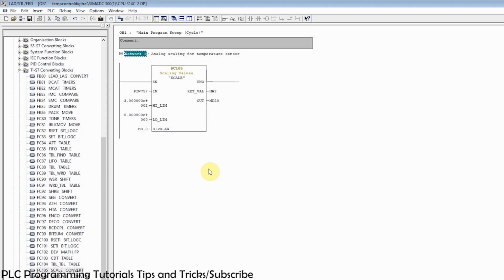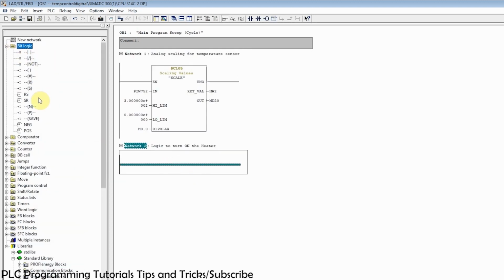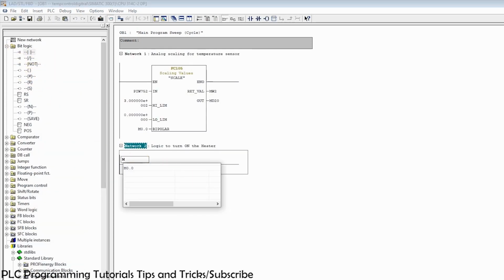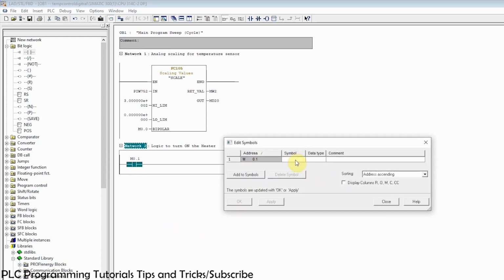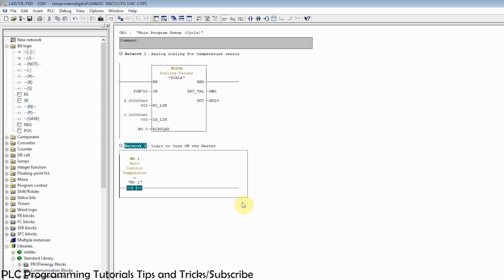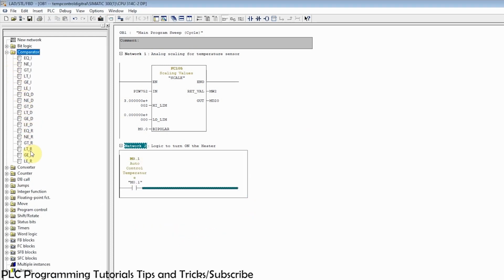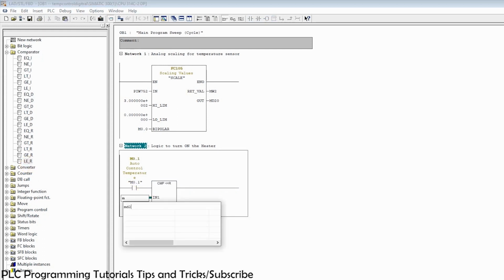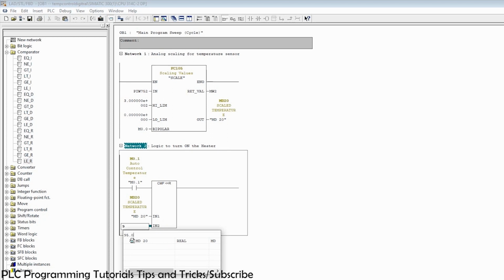In network number 2, we will make a ladder logic to turn on the heater coil. First, we will insert the bit M0.1 to auto start the temperature control. Next, we will insert less than equal to function. This function will compare MD20 current temperature with the 95.0 degrees Celsius. Whenever the temperature is less than 95.0 degrees Celsius, this function gets activated.